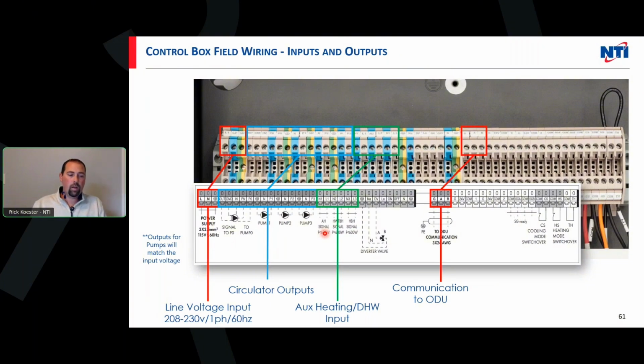So that's going to be going from our indoor to our outdoor box. We've got to make sure this is a 3-wire with a ground, and it is a twisted shielded wire. So we do have to make sure that they're grounding this so that there is no communication interference and we don't get any errors.